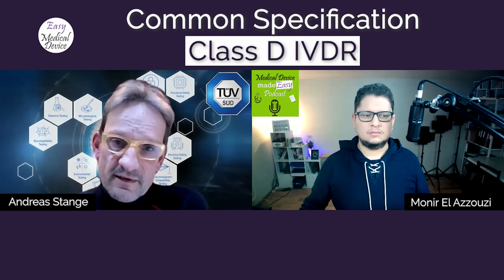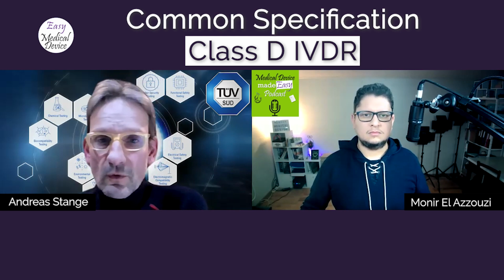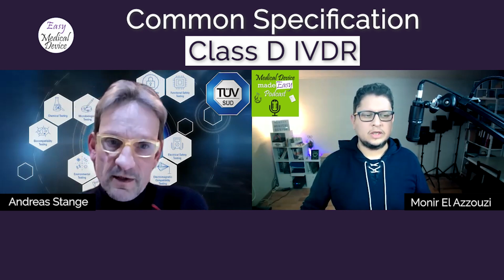Then the notified body needs to consult with the expert panels, and there we then receive the opinion of the expert panels, and this basically establishes a sort of state-of-the-art or benchmark. And this benchmark will then need to be met by the next devices which are certified. So that is the mechanism for these Class D devices where there are no common specifications available.